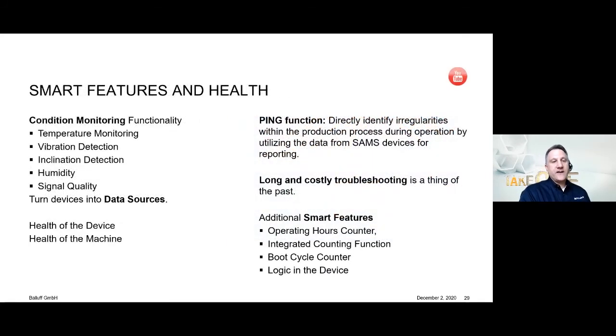We're talking about the health of the device and the health of the machine, and being able to do that in a couple different ways, starting with having condition monitoring functionality or parameters in each device, such as temperature, vibration, inclination, humidity, signal quality. All of these condition monitoring parameters will be available in all the devices and are configured and addressed the same way. So now you have the primary sensing function of the device, which could be object detection or proximity or position, and you have these condition monitoring values as a secondary function. And so now you really have data sources of the performance of the machine through these devices.